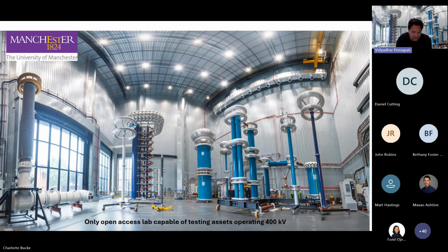Now, what you see here are larger voltages. However, across the door, we also have smaller labs that allow us to test at material level - down to oil, down to XLPE, down to gas - more material and analysis that gives you an understanding of how they fail, how they age in the future, what your condition monitoring is, what kind of sampling technology you need if you want to keep something running for 15, 20, 30 years.